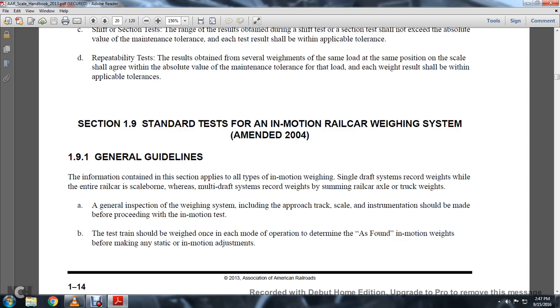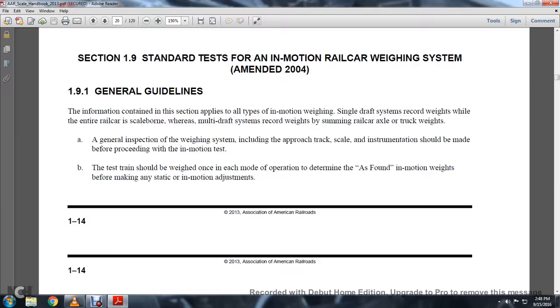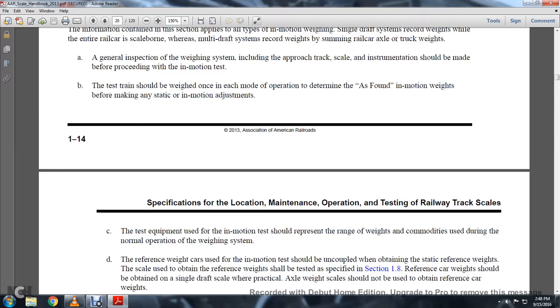A general inspection of the weighing system, including the approaching track and scale instrumentation, should be performed prior to the in-motion test. Test cars should be weighed once in each mode of operation as found before making any static or motion adjustments.